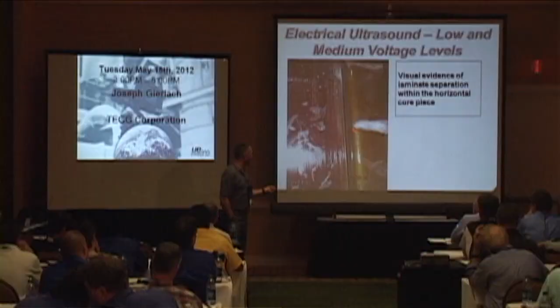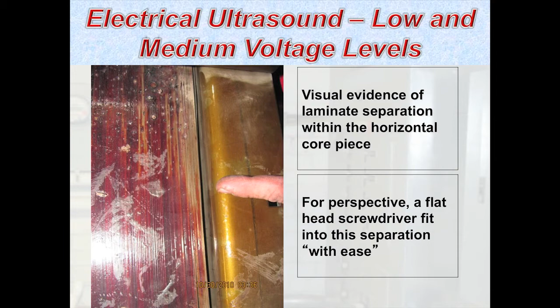Now the root of why we were hearing this is becoming more evident, what we heard in the ultraprobe. There were signs, we heard it with our ears, but looking right here, this is a separation in those laminates. For perspective, the guy out there could stick a flathead screwdriver down into the slot. This area is supposed to be bonded with that steel. Now these laminates have separated, haven't they?